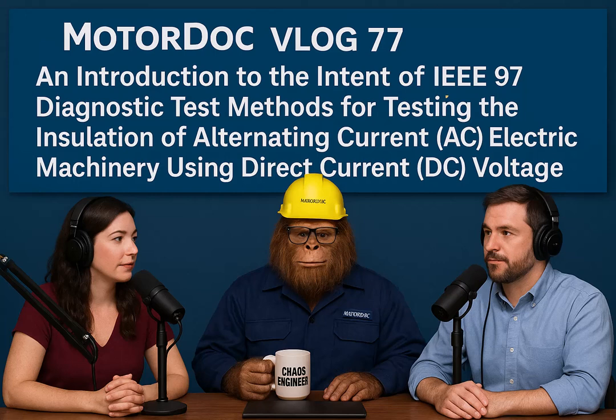Makes sense. And noise can then interfere, like electrical noise from the tester or nearby equipment. The guide acknowledges noise is definitely a factor. Noise from the instrument's own internal power supply switching, sometimes called rail noise, can cause fluctuations or fuzziness in the IRP plot, especially when you're measuring very high resistance values. This could potentially mask the true absorption current decay shape or introduce spurious spikes that look like contamination. And external common mode noise, maybe from nearby variable frequency drives, VFDs, or other sources, can also cause spikes and variances. That could potentially be misdiagnosed as contamination.